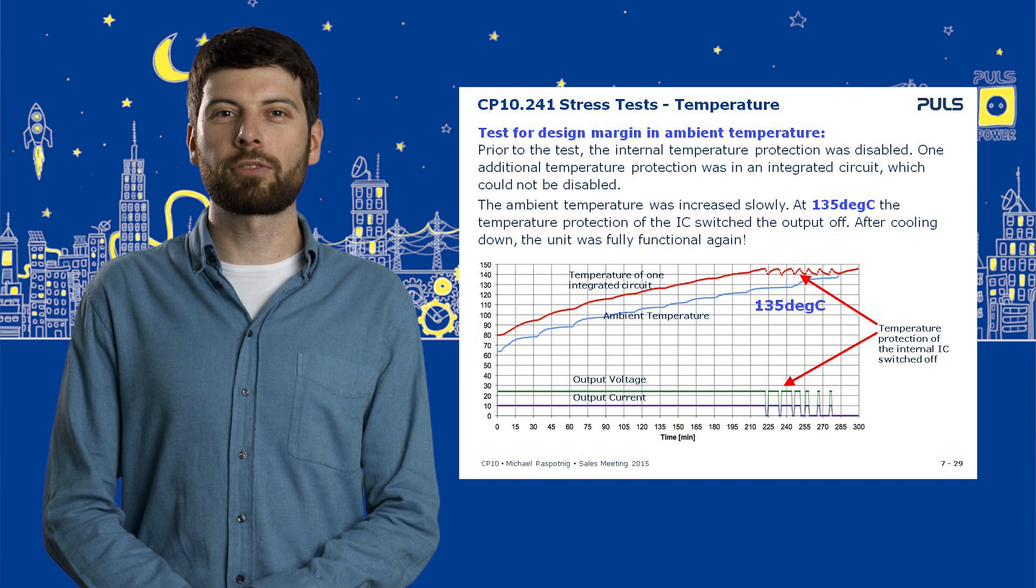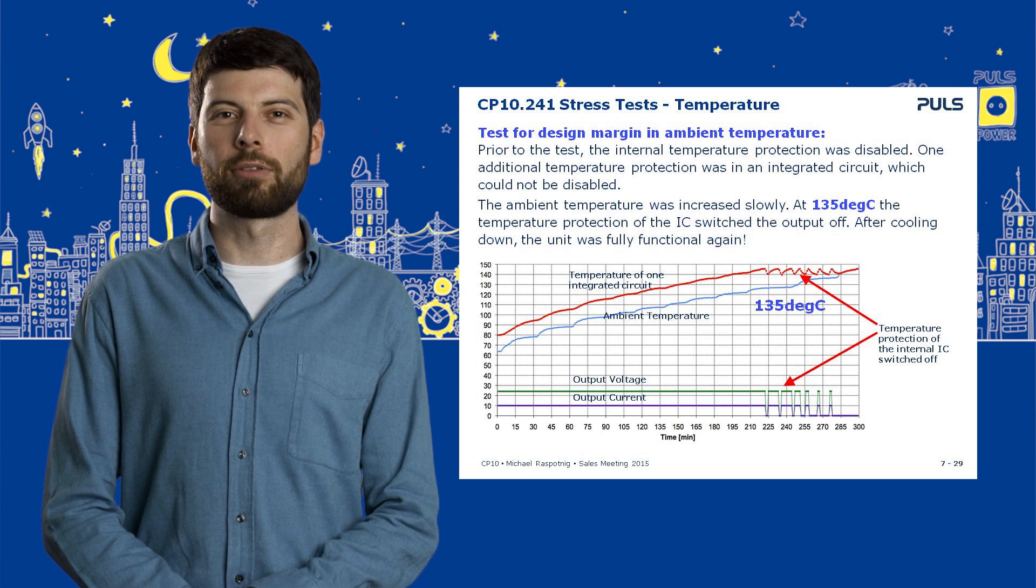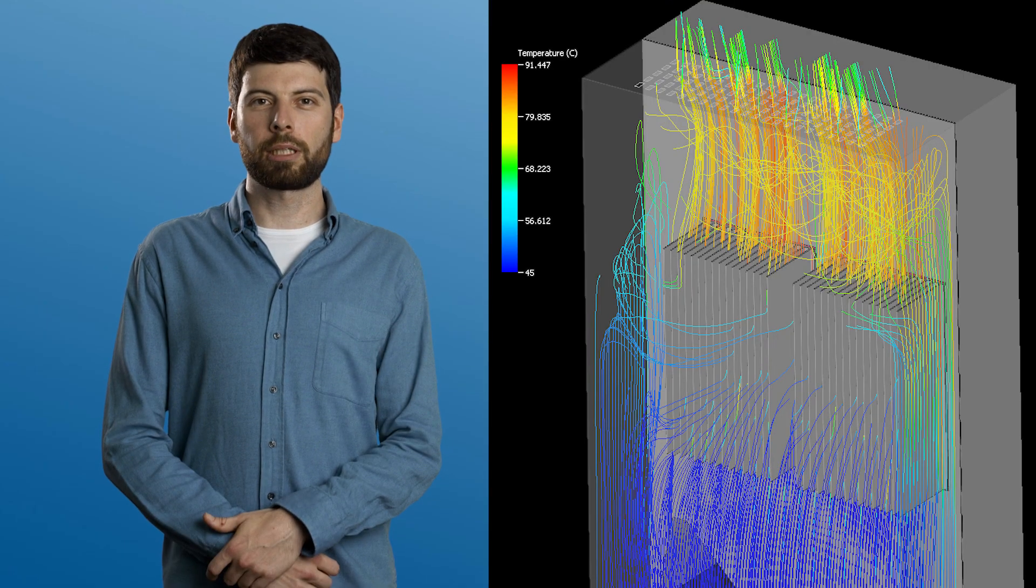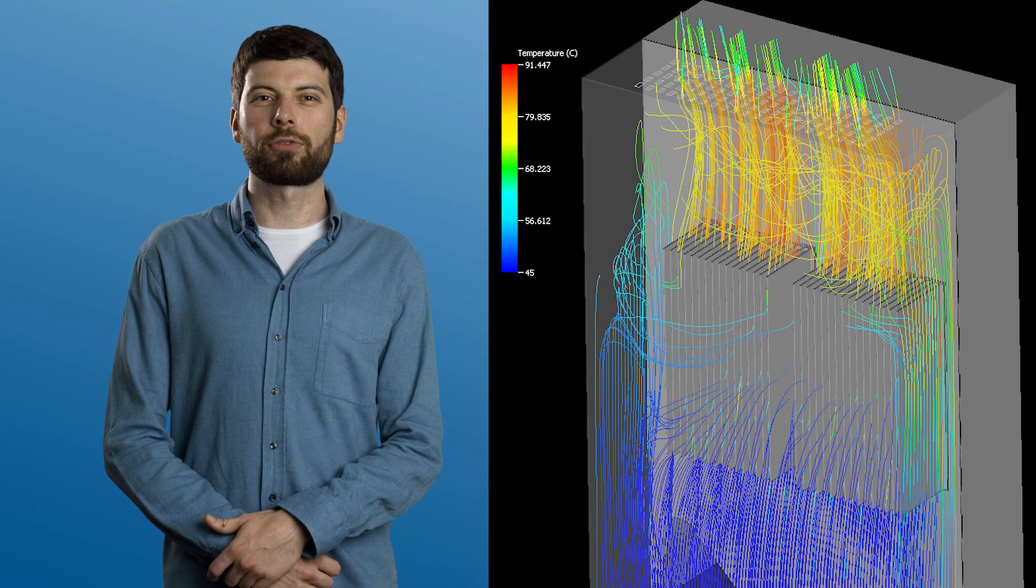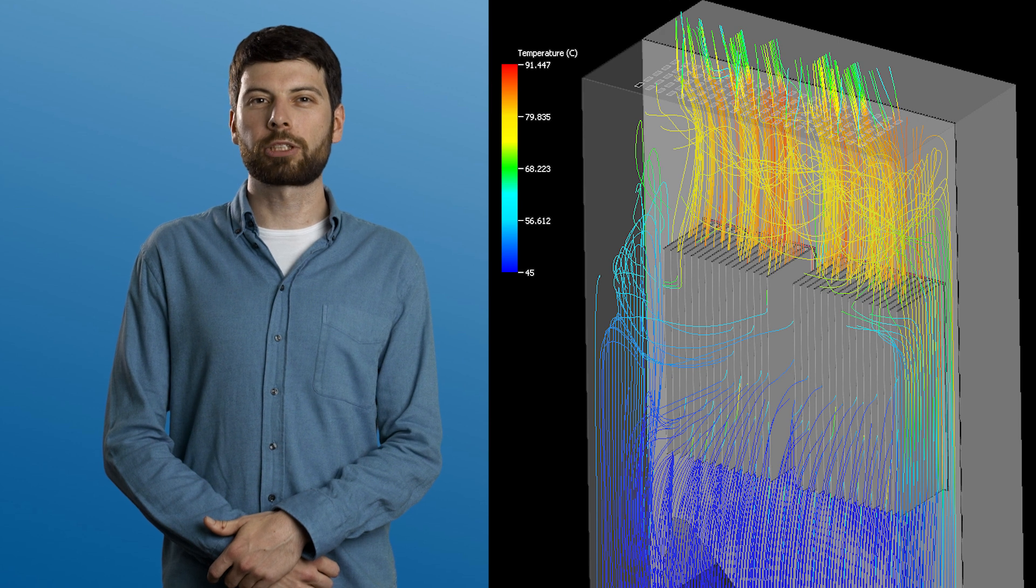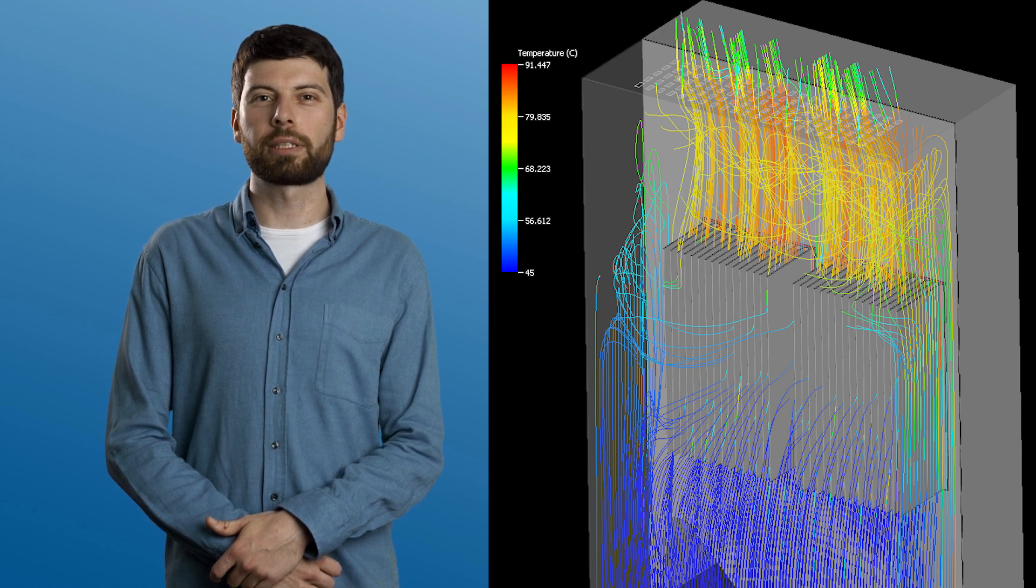We calculate the failure rate based on stress levels subjected to individual components. Temperature stress is the most important factor. 10 degrees Celsius reduction in temperature halves the failure rate.